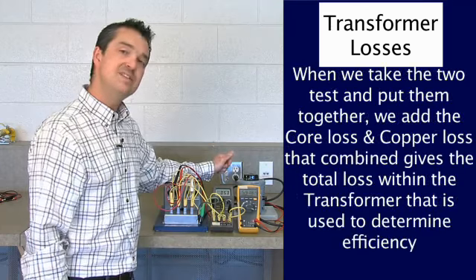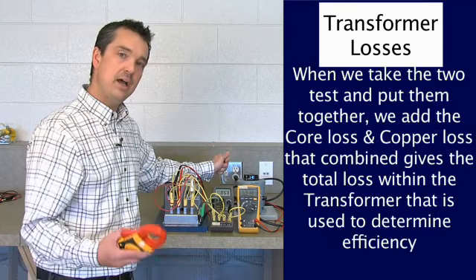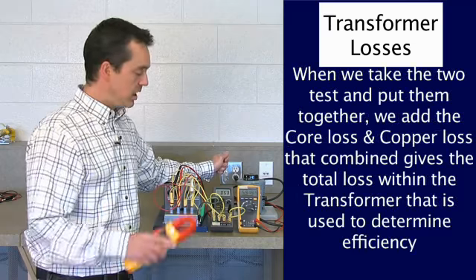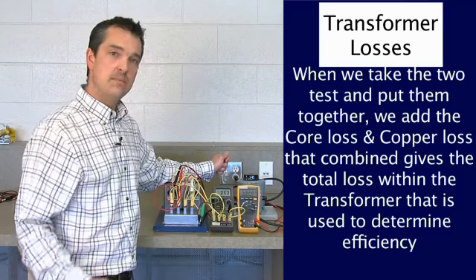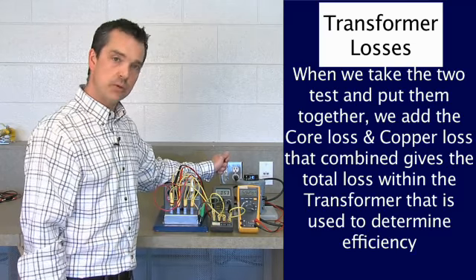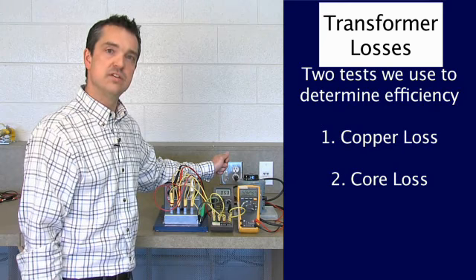And when I take these two tests and I put them together, I add the core loss that I saw as well as the copper loss that I saw, and that put together gives you a total loss within the transformer that is used to determine efficiency. Those are the two tests that we use to determine losses and efficiency in a transformer.